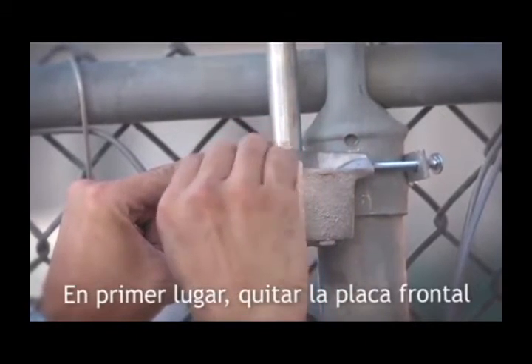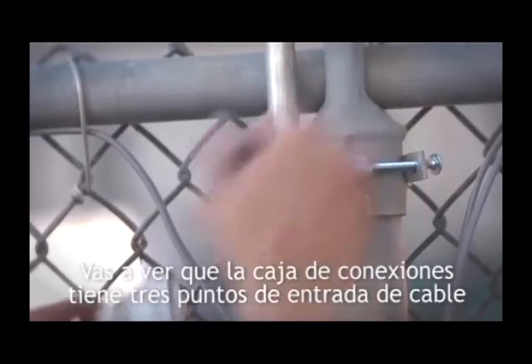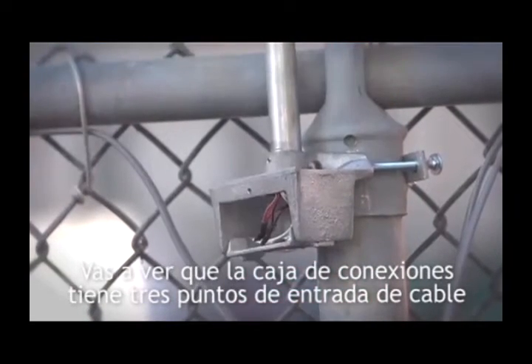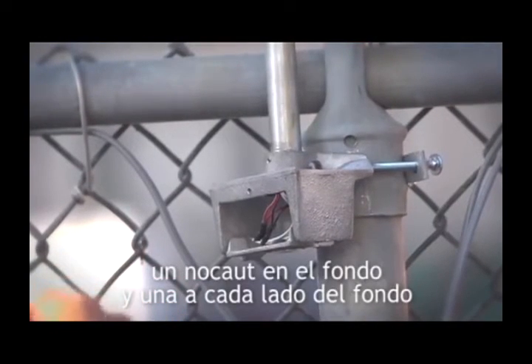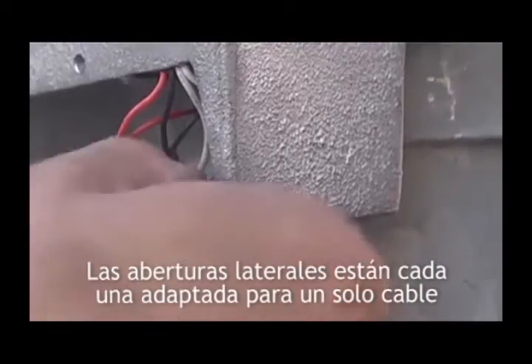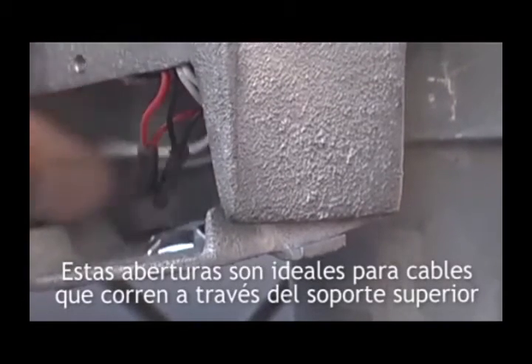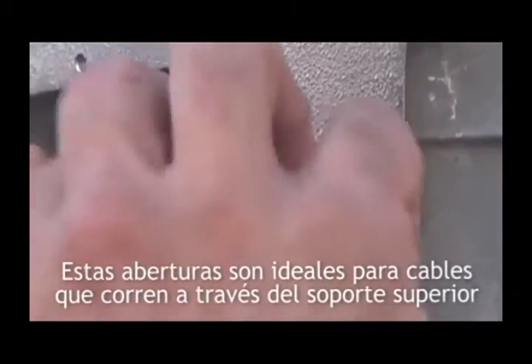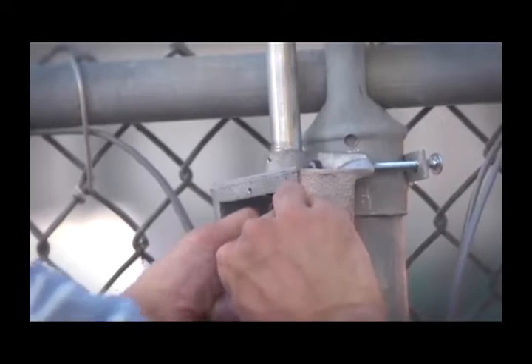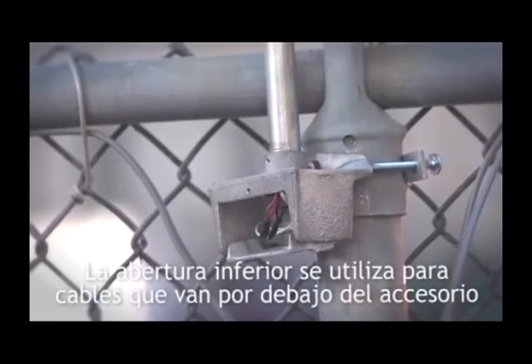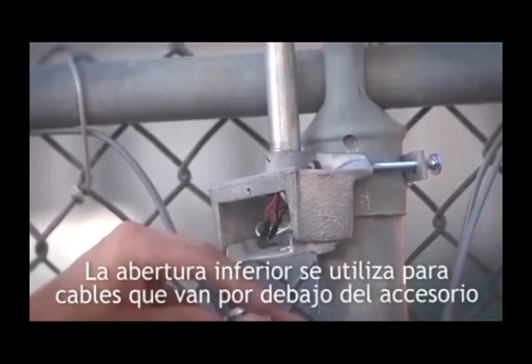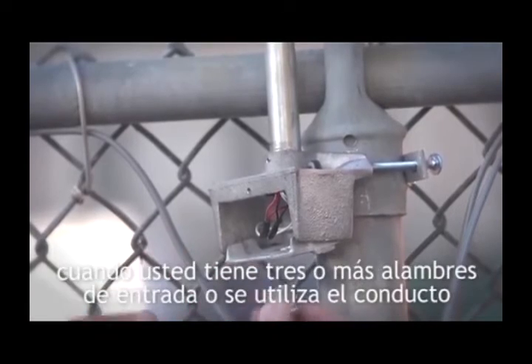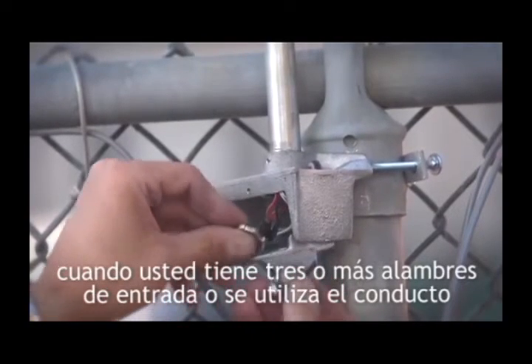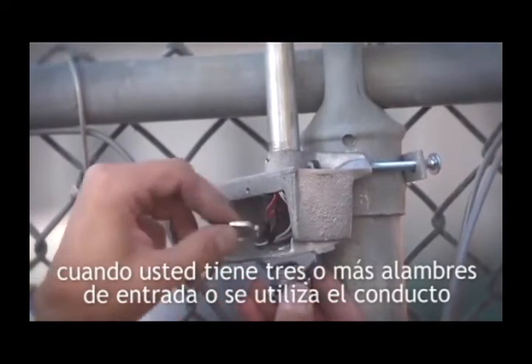First, remove the faceplate. You'll see that the junction box has 3 points of wire ingress, a knockout on the bottom and one on each bottom side. The side openings are each suited for a single wire. These openings are ideal for wires running across the top support. The bottom opening is used for wires running from locations below the fixture, or when you have 3 or more entering wires, or when you use conduit.